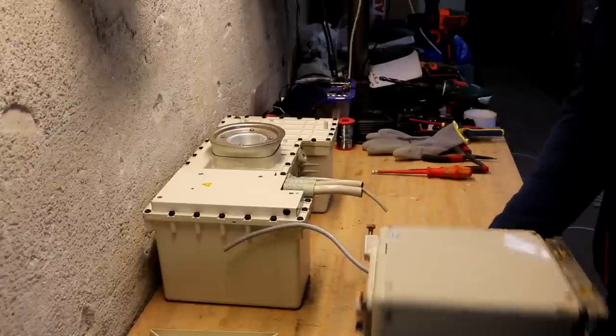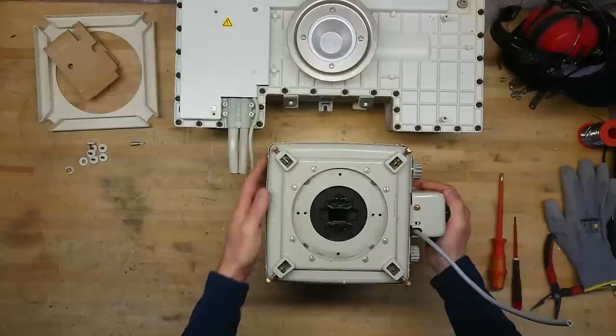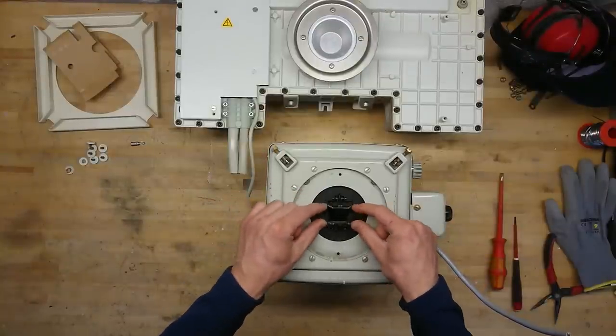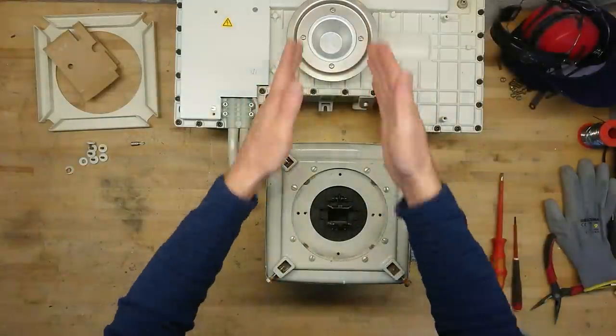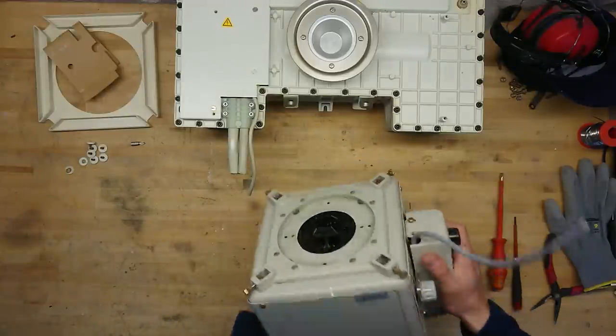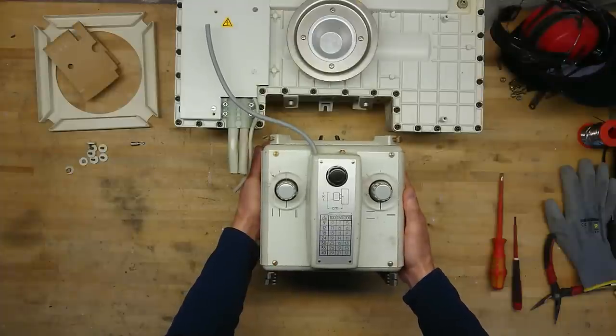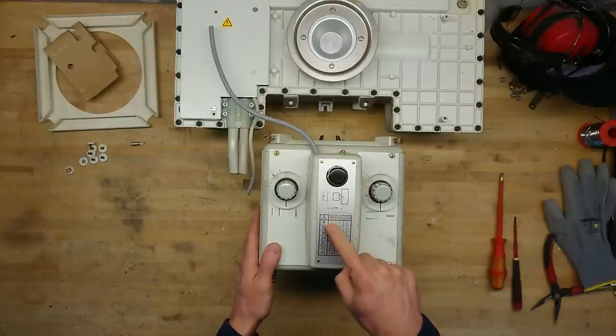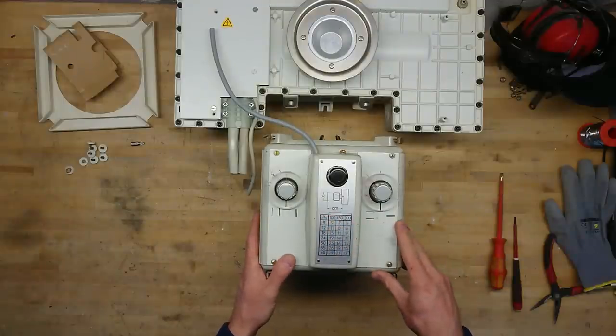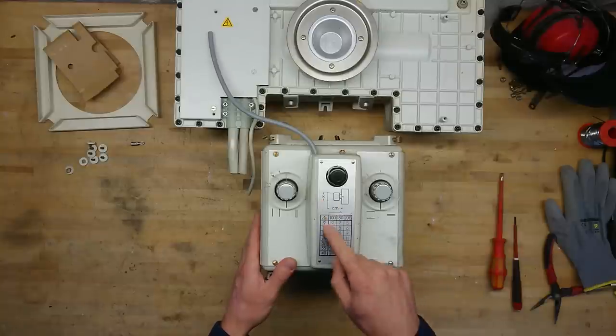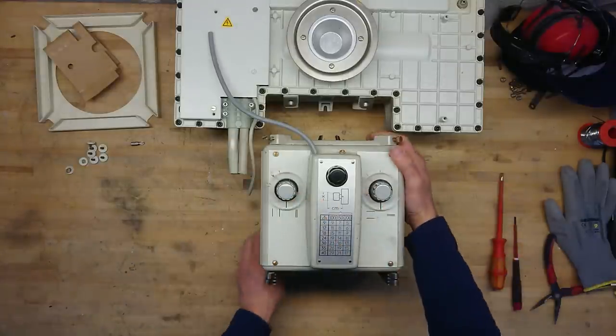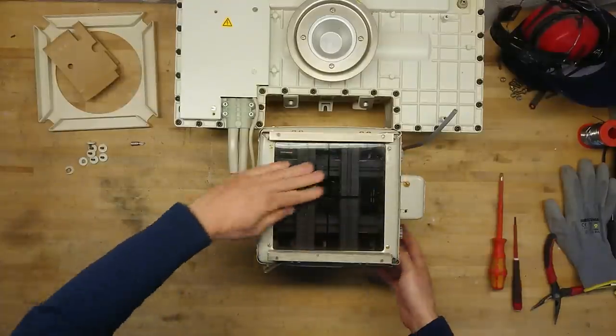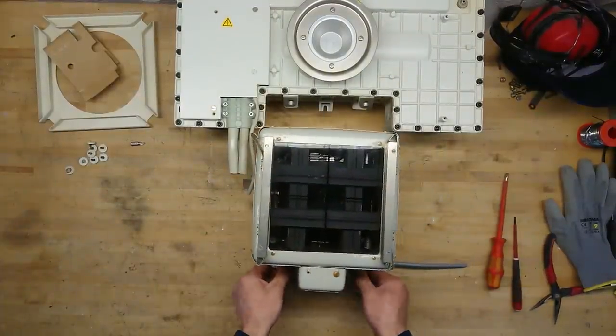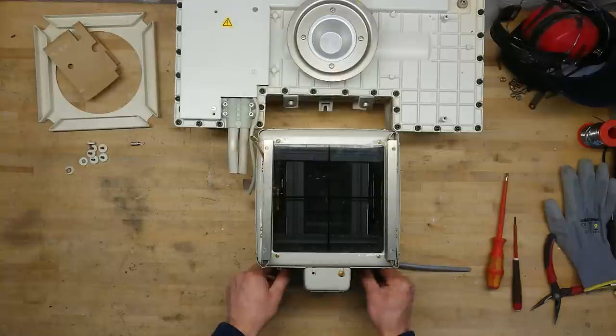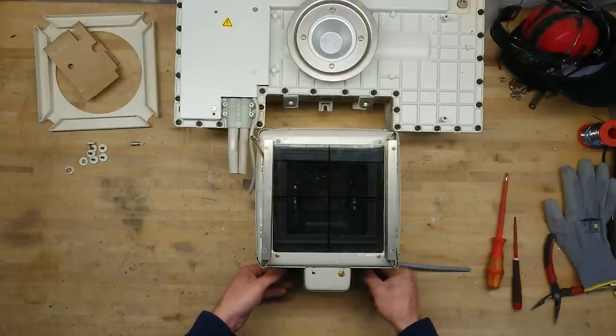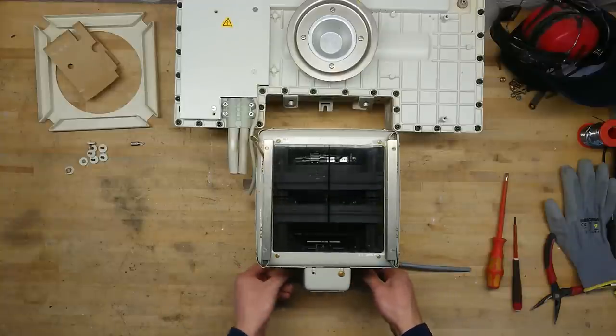Take a look at the collimator. See, it's actually a quite narrow port that it has here to guide the X-rays inside, for these dials here at the side. And see here, depending on if you're 1 meter, 1.5 or 2 meters from the person, you have to adjust the window according to these dials here. Now, these dials move around the blinds in here, so that way you can shape the area at which the patient is radiated.